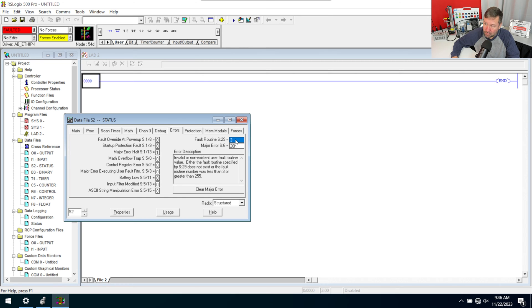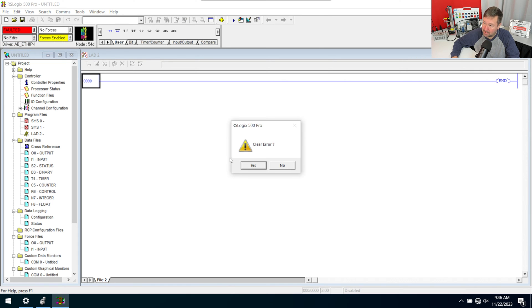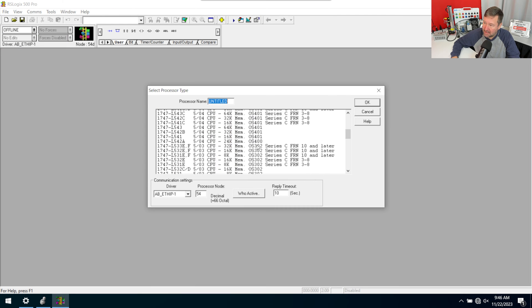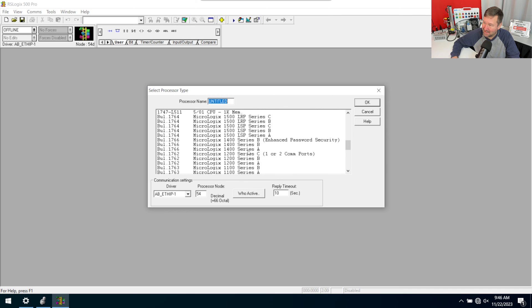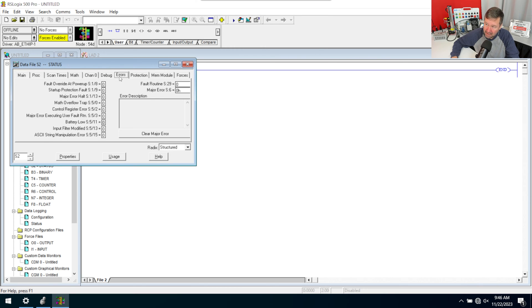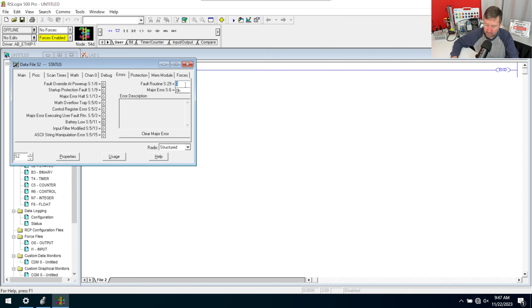Here is that fault routine number. Let's do this from scratch so we can see how you end up in this situation. I'm going to clear that fault, then create a new file and select a Micrologix 1400 — this one's a series A. Then we'll go to the status S2 data table and go to the errors. I'm betting that you have a three there, because that is listed as the user fault routine description. So if I just put a three here...